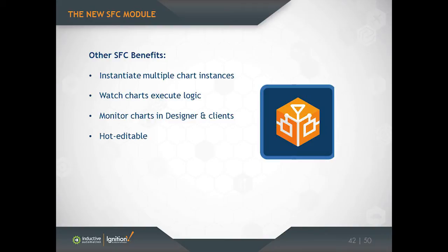Another thing that SFCs are really good at is being monitored. So unlike a script, when you write a script and you run it, the only way to monitor what it's doing is to watch for the side effects that that script creates. So maybe you know at a certain part in the script it's going to log a message or it's going to write to a tag, and so you watch for those things happening. With a sequential function chart, you can just watch the chart execute because the chart is defined in such a visual nature that you can just watch these things run. And that makes it really easy to debug these things and learn how they work because you can see them so directly. And that monitoring is done either in the Ignition Designer or in a Vision Client.